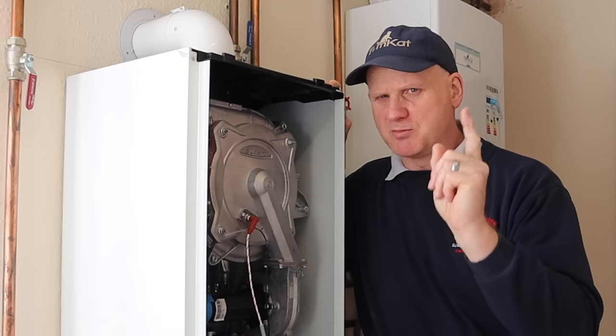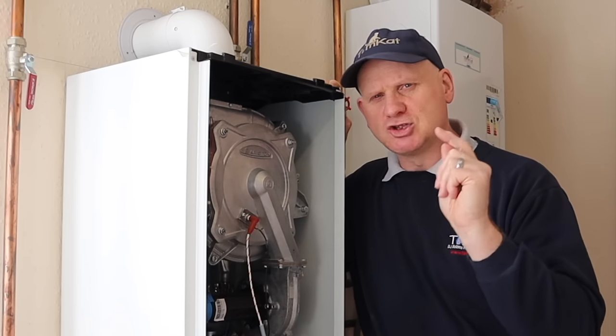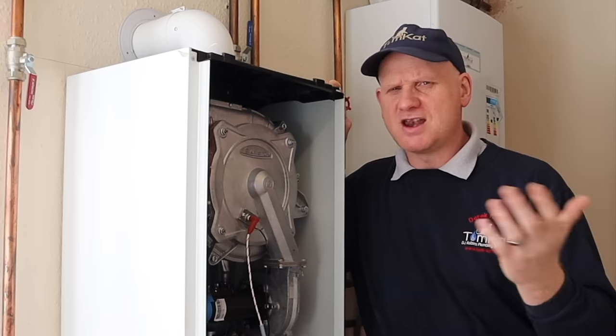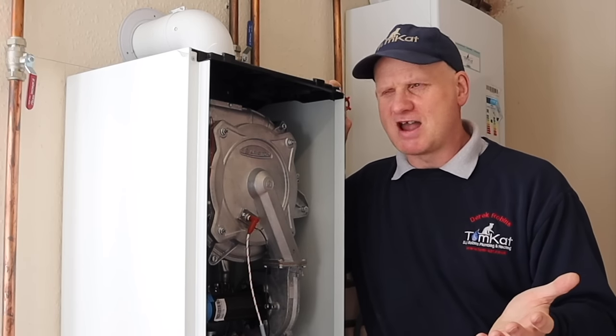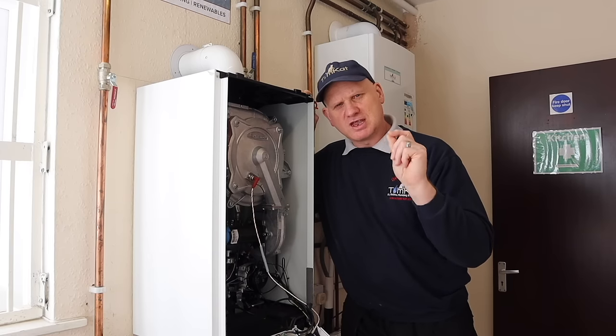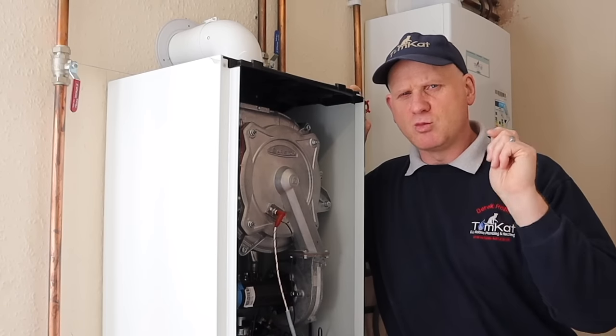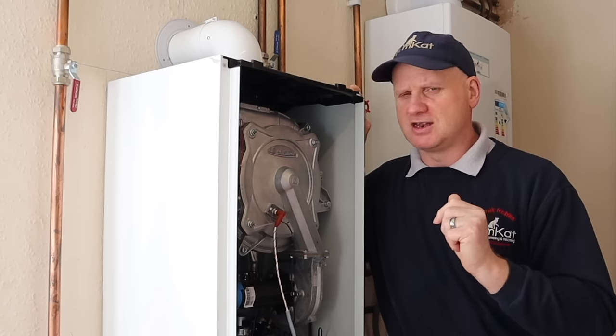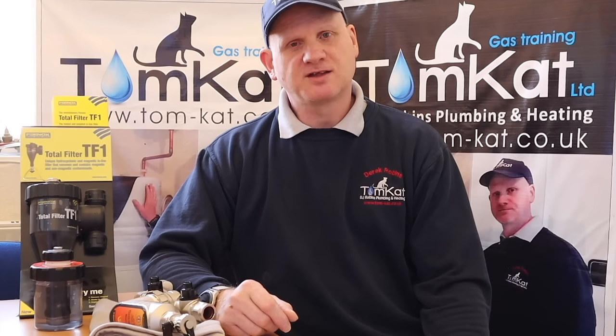But, and this is the big but, which a lot of engineers don't do, they don't modulate the boilers down on central heating. They leave them on full whack. So that means they're not saving any energy, and they're not saving the environment, and they're not saving the planet. So actually fully commissioning the boiler correctly, with the controls, is the only way you are going to save this energy and this planet. Now, most of our customers pay little attention to the health of their boiler until it stops working. The high cost of fixing this problem could have been averted by just having the boiler checked and serviced every year. Little is understood about the damage that is caused by problems with system water by most engineers.